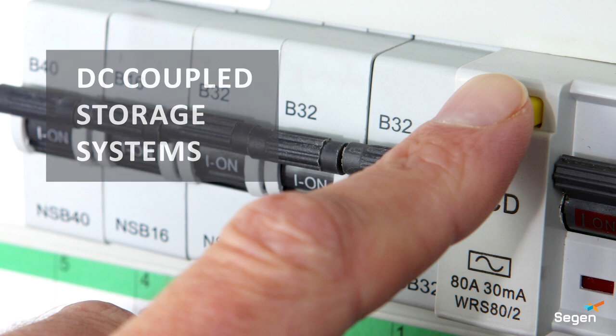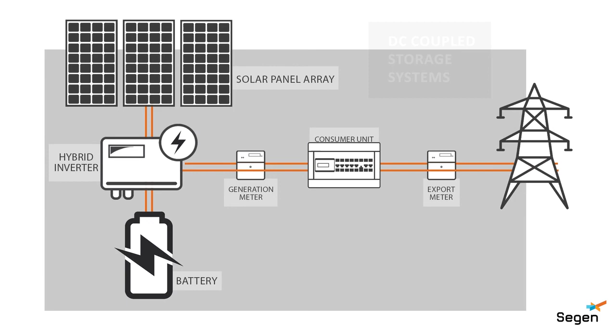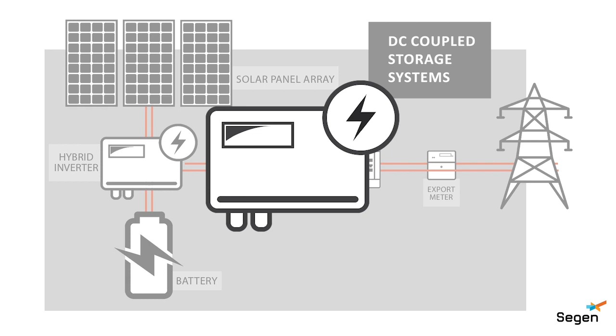DC-coupled hybrid storage solutions are connected to the DC side of a PV system. This means that there's no additional AC-DC energy conversion needed. Most DC-coupled storage solutions are now hybrid inverters. This means that the inverter is a hybrid of the two technologies, with the PV inverter and the battery controller in one single unit. So let's get on to system sizing.